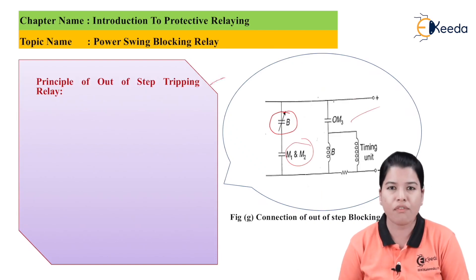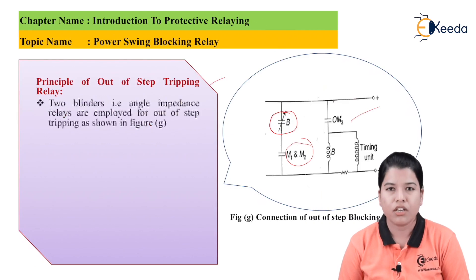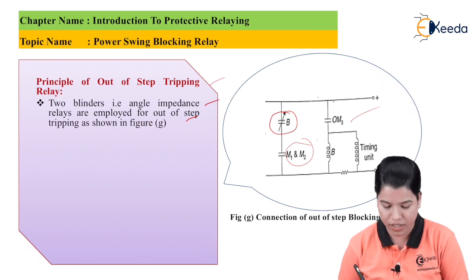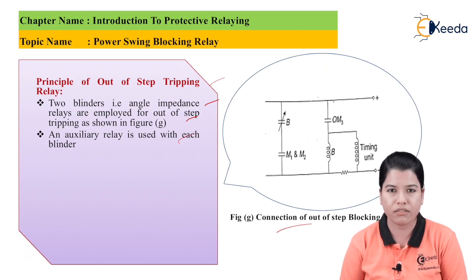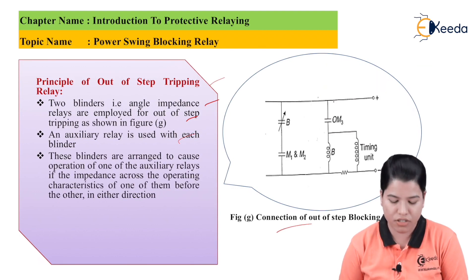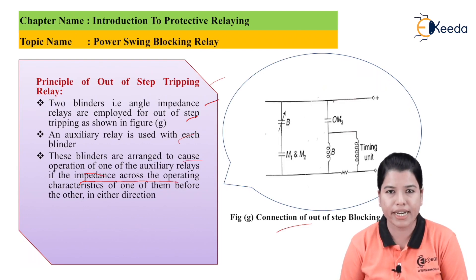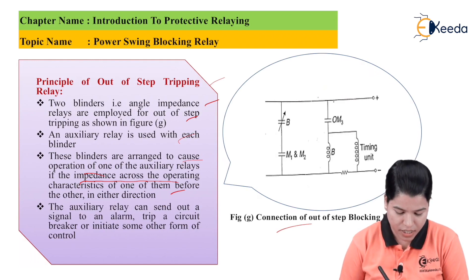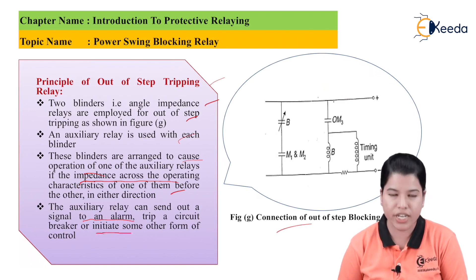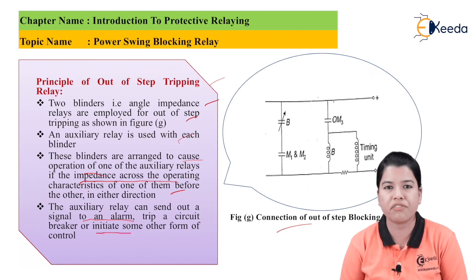Now let us study the principle of out-of-step tripping. Two blinders, which are angle impedance relays, are employed for out-of-step tripping as shown in figure G, and an auxiliary relay is used with each blinder. These blinders are arranged to cause the operation of one of the auxiliary relays if the impedance crosses the operating characteristic of one blinder before the other, in either direction. The auxiliary relay can then send a signal to an alarm, trip a circuit, or initiate some other form of control.